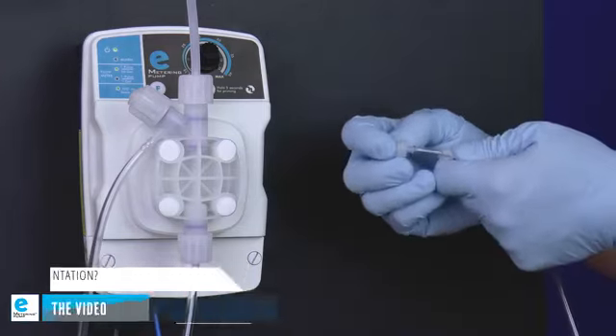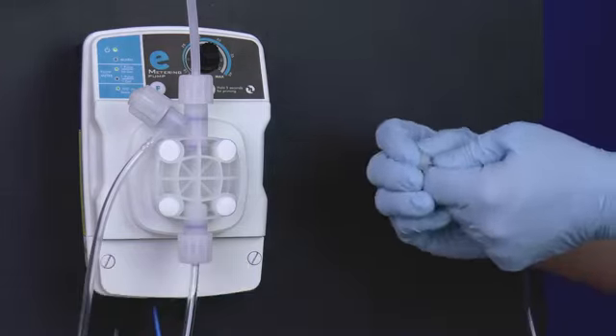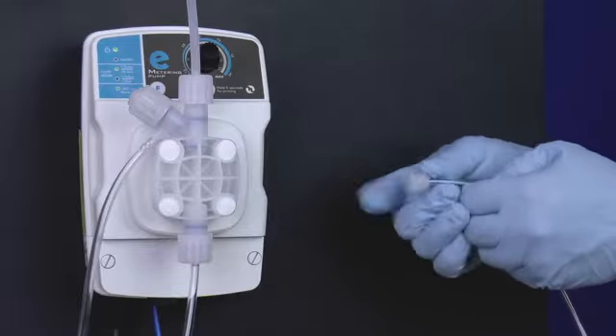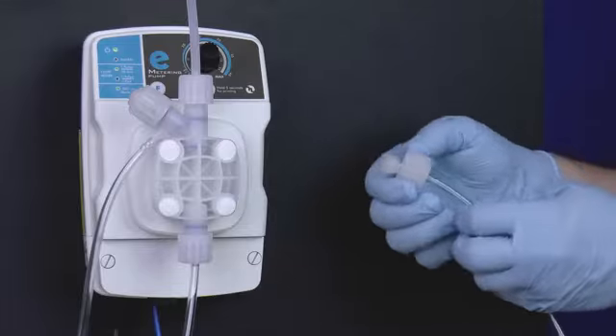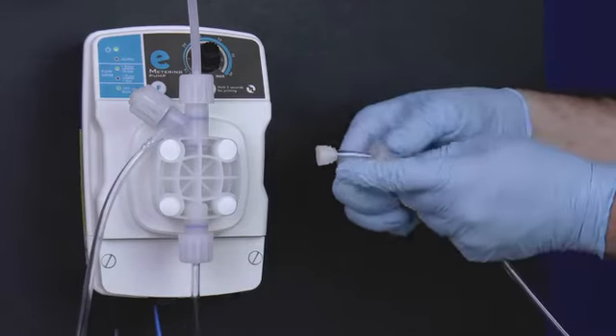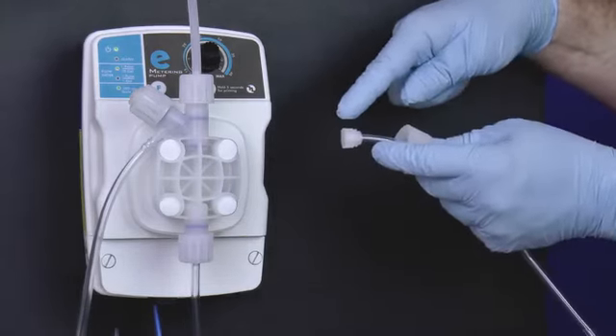Reattach the foot filter tubing connections onto the loose end of the tube. Be mindful of their orientation. Push the collar and nozzle together as close as possible. Pull the tube nut toward the nozzle to compress the collar and nozzle tight together, forming a ferrule connection.